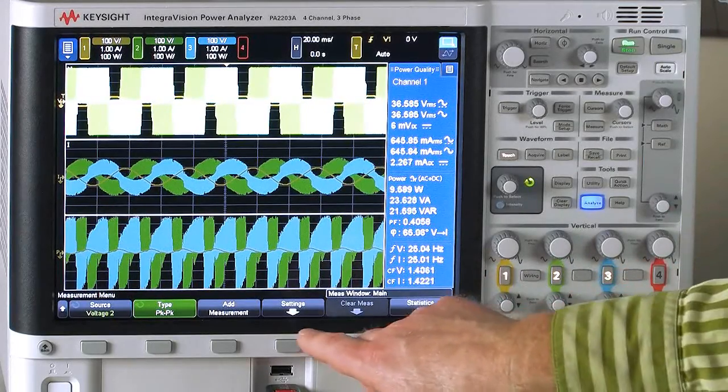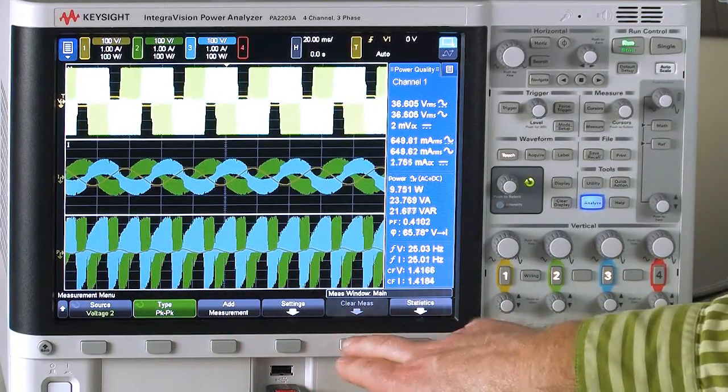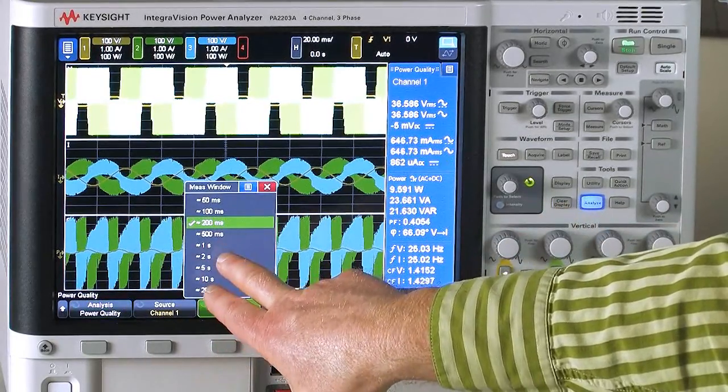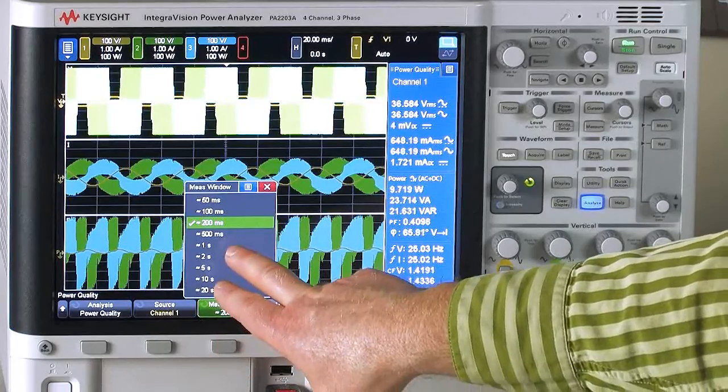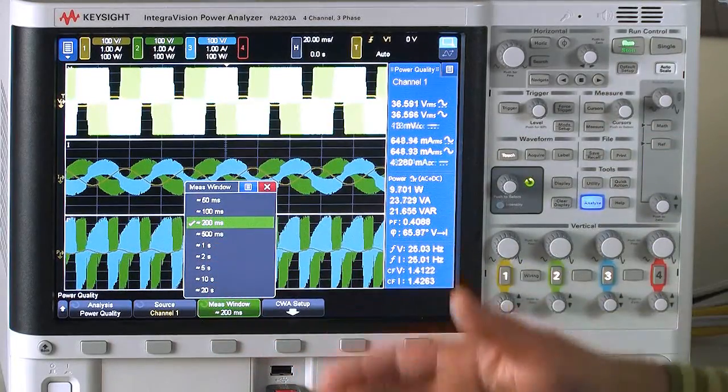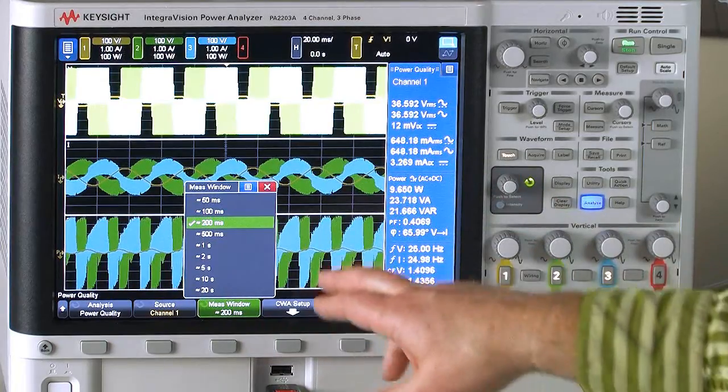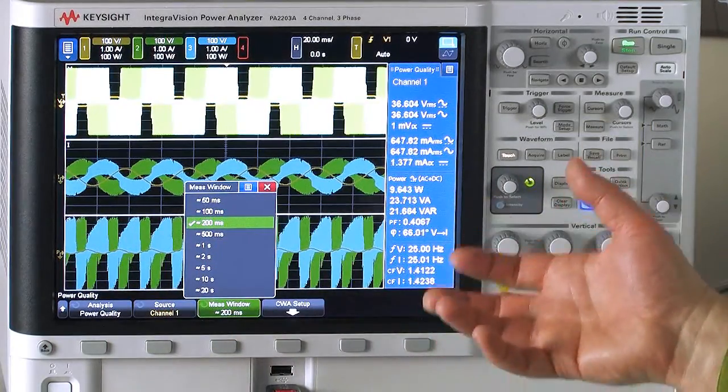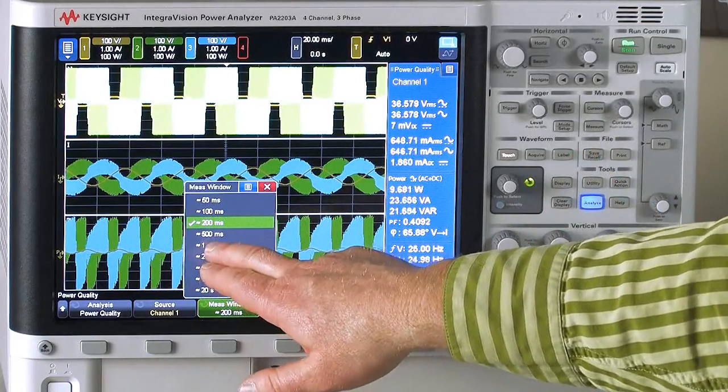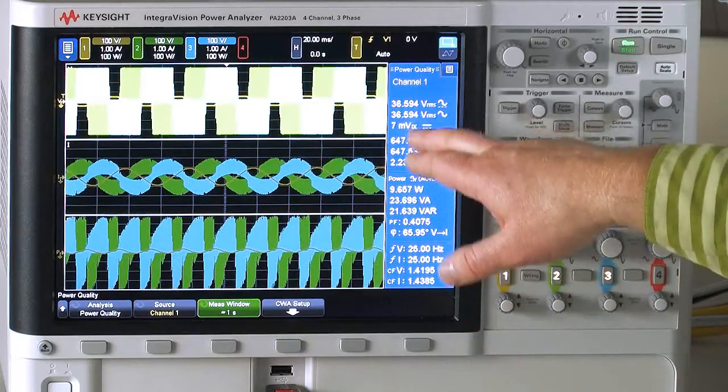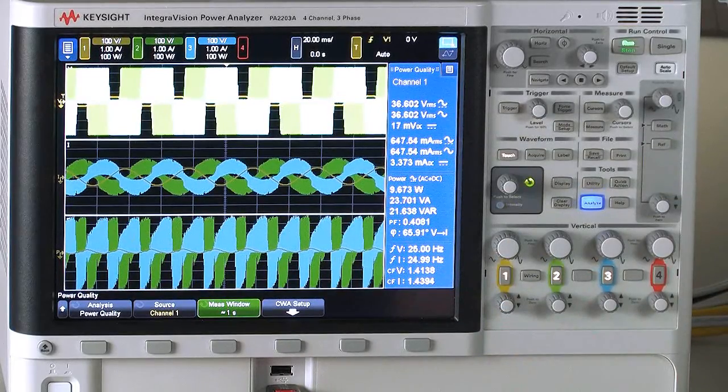So another thing that I can define here is I can change the window of this analysis. Right now it's at 200 milliseconds. That's okay for a 60 hertz signal. As you go lower and lower in frequency, you need a longer window to get a good measurement to average over a number of cycles. And so I'm going to change that to a one-second window and that should get me a very nice, stable measurement there.